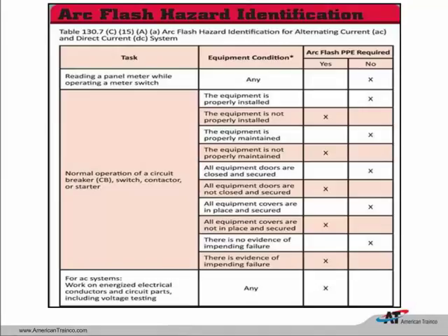The equipment was properly installed. You can see that there is an X underneath the word no. So, arc flash PPE required? Equipment was properly installed? No, I don't need to wear arc flash PPE in that case. Then we have to make sure that the equipment was installed properly, and if it was, then we're great. If the equipment was properly maintained, that's a key now. If the answer to that is no, which I suspect most of our equipment probably has not been maintained according to the manufacturer's instructions, if we answer that the equipment is not properly maintained with a yes, you can see that now we are going to have arc flash PPE. So that to me is the key question. Has the equipment been properly maintained?